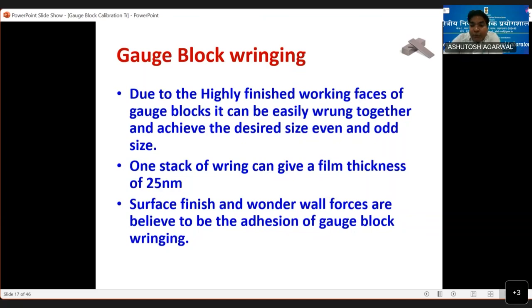Many technicians who are new, and even after experience, are not able to wring properly. And measurement uncertainty is, most of the time, because of wringing. Due to the highly finished working faces of the gauge block, it can be easily wrung. Wrung means stick together and achieve the desired size, even an odd size. I will tell you how to achieve the size also.